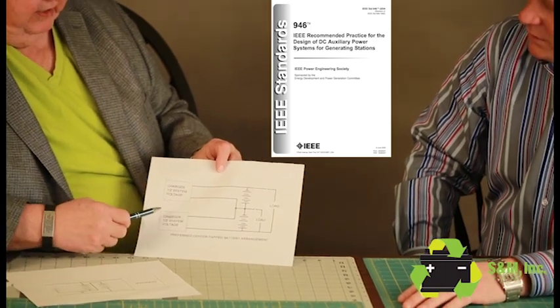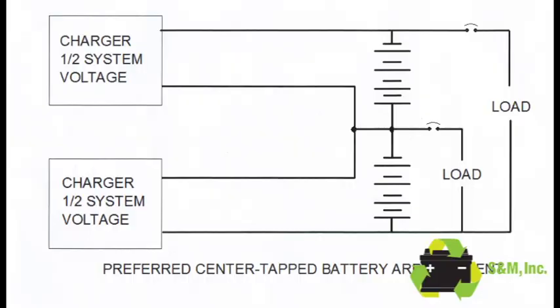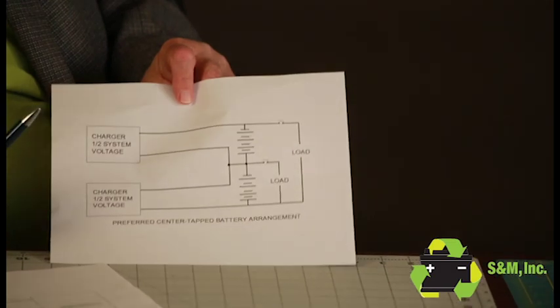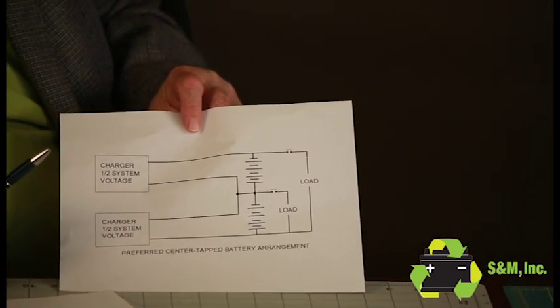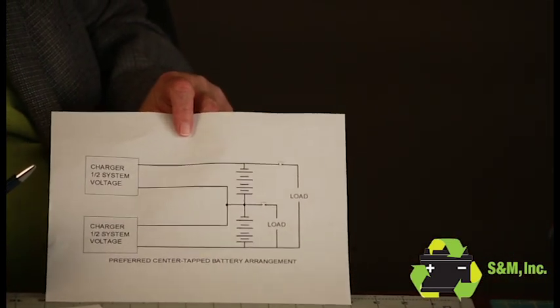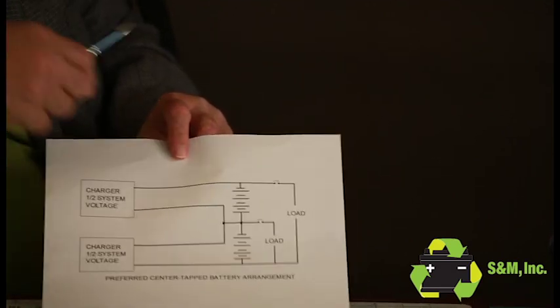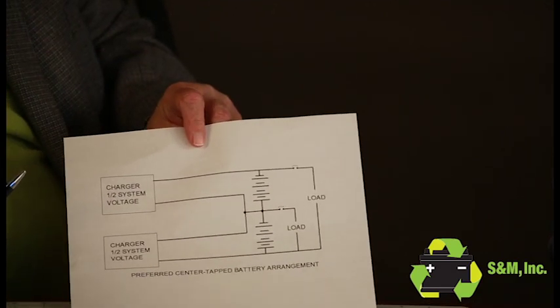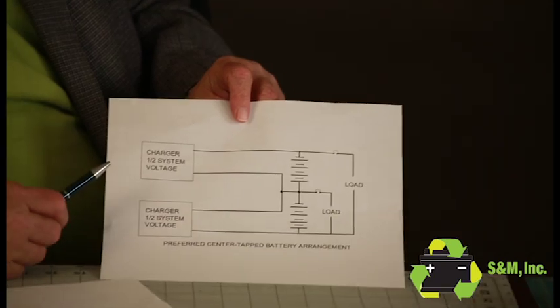In a lot of utilities, if they have two different voltages, 125 and 250, they'll tie batteries center tap this way, take a charger and another charger, put them in series across it, and come out through a circuit breaker to the 125 volt load, or through a circuit breaker to the 250 volt load. That gives them some flexibility. There are other ways they've done it over the years, but this is the more preferred arrangement in a utility.